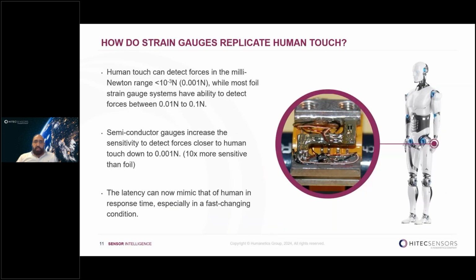So how do strain gauges replicate human touch? Human touch can detect forces in the millinewton range, less than 10 to the minus 3 newtons, which is approximately one thousandth of a newton. While most foil strain gauge systems have the ability to detect forces between 0.01 and 0.1 newtons, semiconductor gauges increase the sensitivity to detect forces closer to human touch, down to 0.001 newtons.